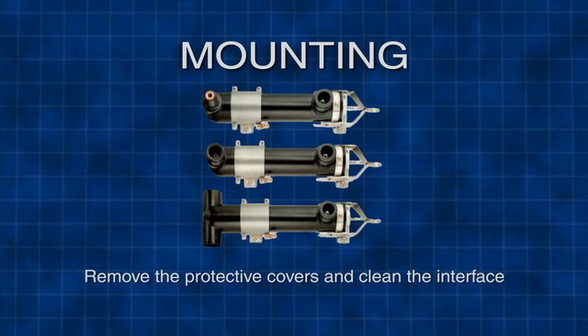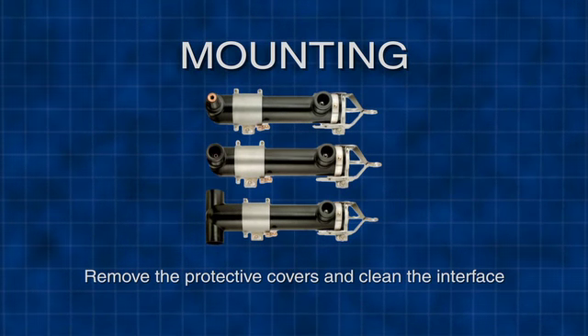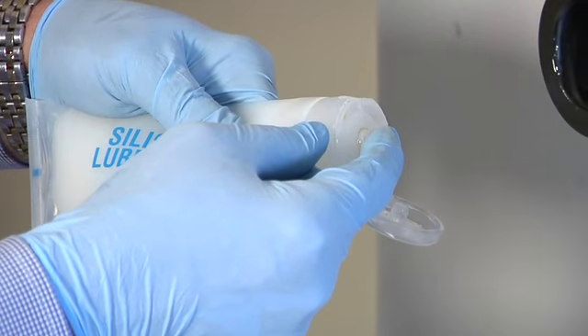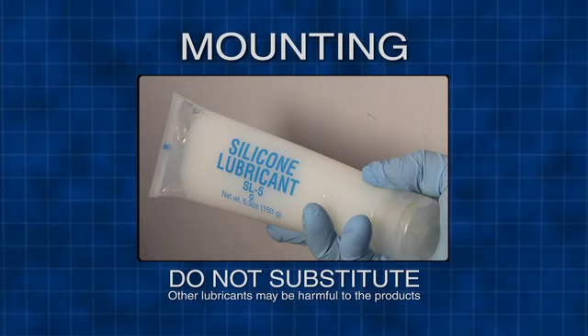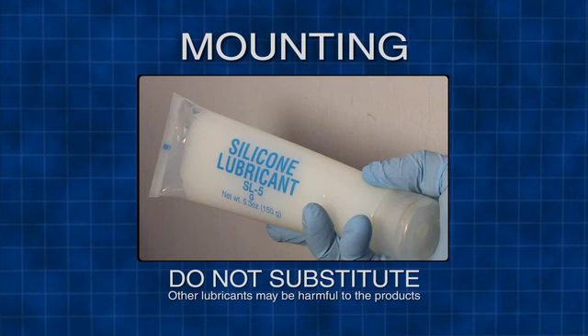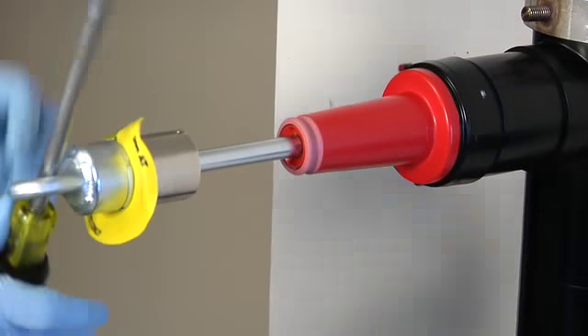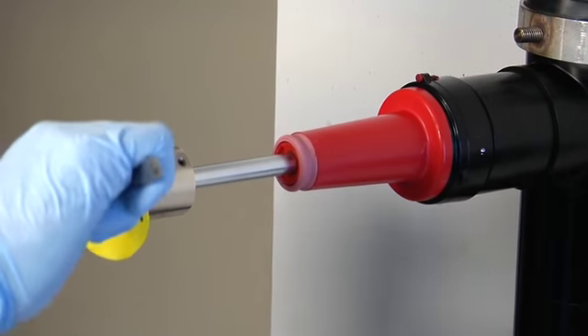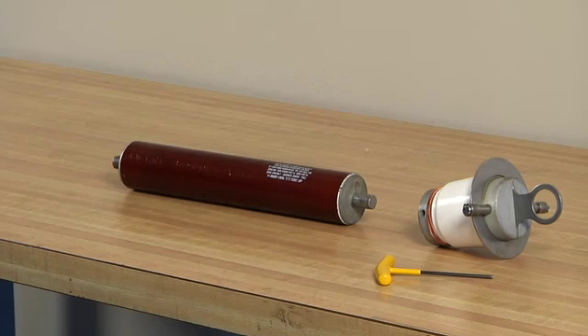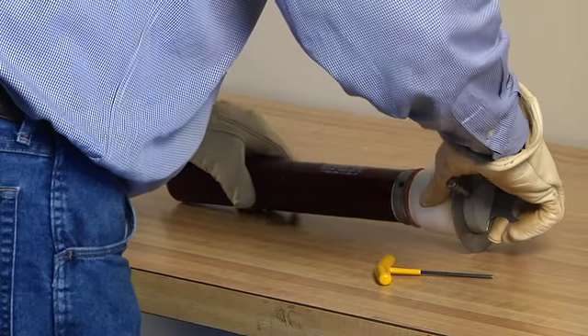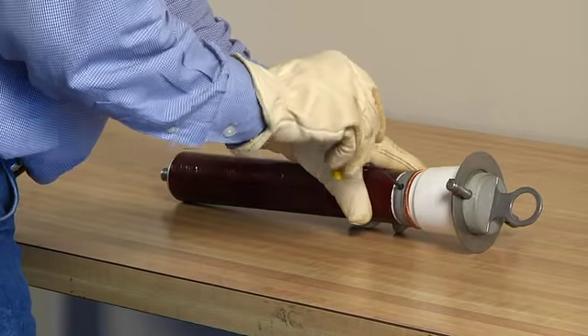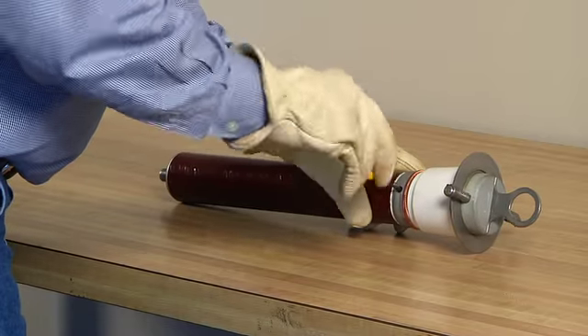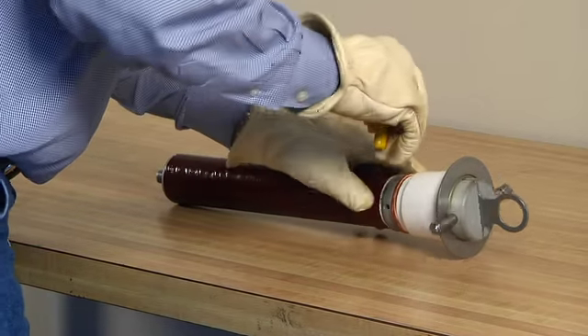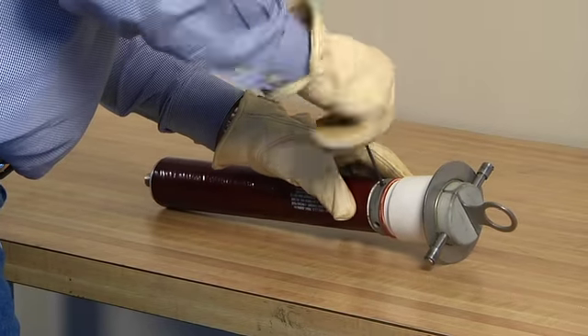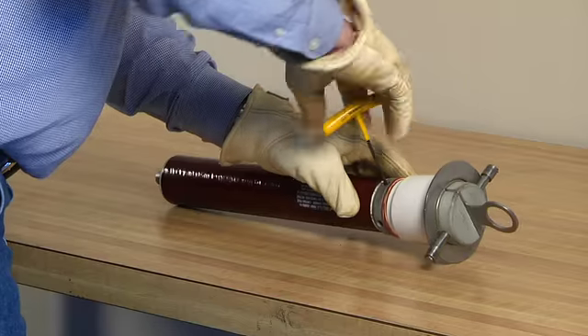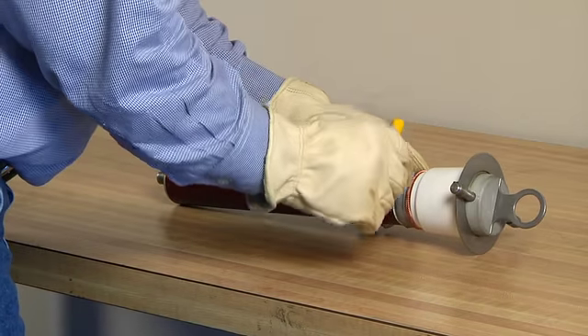Prior to installing bushings or connectors, remove the protective covers and clean the interface. Lubricate the interface with Elastimold approved lubricant only. Do not substitute. Other lubricants may be harmful to the products. Install additional connectors or bushings by following the instructions included with those products. To begin installation, insert one end of the fuse into the end plug until it bottoms. If a 5.5 kV or 8.3 kV fuse is used in a size 5B holder with an approved extension, place the extension end into the end plug, not the fuse end. Hand tighten the 2 set screws with a 1/8 inch Allen wrench.